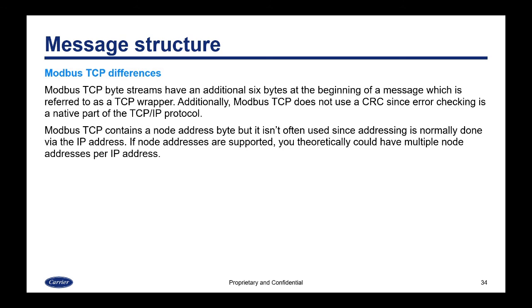Modbus TCP byte streams have an additional six bytes at the beginning of a message, referred to as a TCP wrapper. Additionally, Modbus TCP does not use a CRC since error checking is a native part of the TCP/IP protocol. Modbus TCP contains a node address byte, but it isn't often used since addressing is normally done with the IP address. If node addresses are supported, you theoretically could have multiple node addresses per IP address.